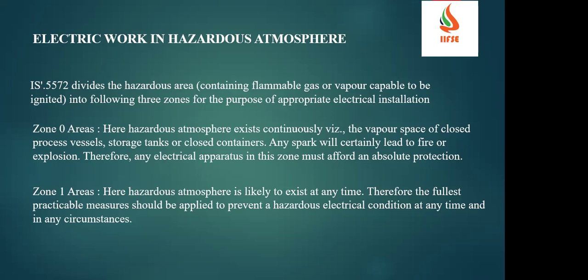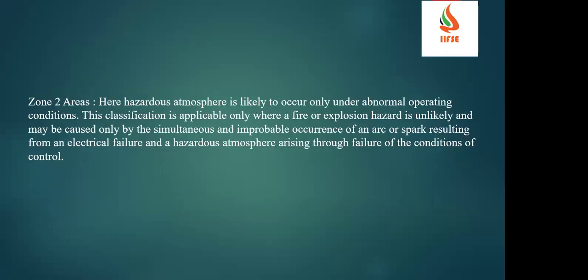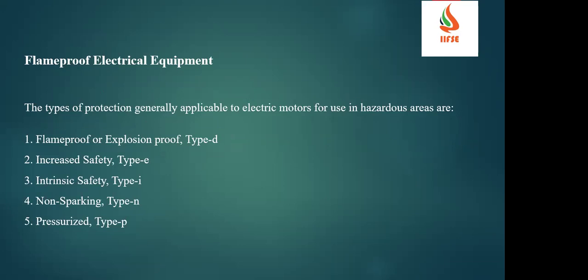Therefore, the fullest practicable measure should be applied to prevent hazardous electrical conditions at any time and under any circumstances. Here, anytime it may happen. This hazardous atmosphere is not continuously present, but anytime it may happen. In zone 2, the hazardous atmosphere is likely to occur only under abnormal operating conditions. This classification is applicable only where a fire or explosion hazard is unlikely and may be caused only by the simultaneous or improbable occurrence of an arc or spark resulting from electrical failure, or hazardous atmosphere rising through a failure of condition. In the sense, if any accident happens, in that case this hazardous situation may rise up. Okay, those are the zone classifications.